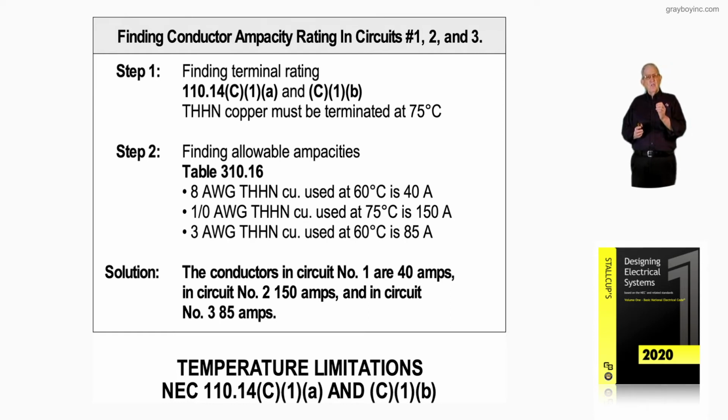But you have to terminate with the ampacity that the terminal allows you to load to a particular terminal rating, which in this case is 60 degrees C.